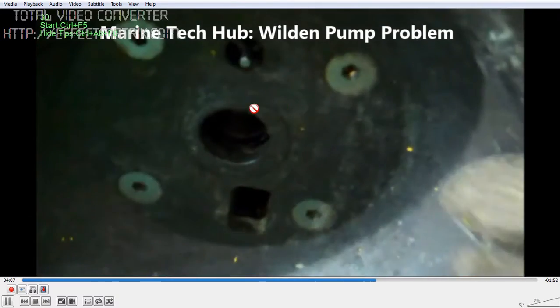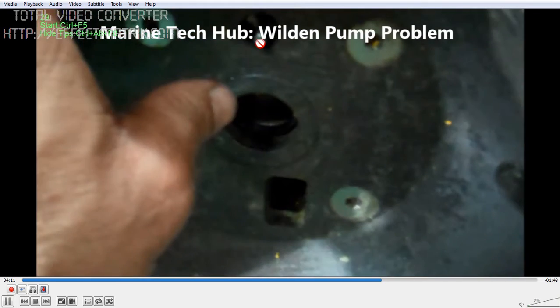One time the spool and diaphragm will push on this side, and the second time it will push on the other side. So this should move freely — if this is not working, your Wilden Pump will not work. If the spool piece is working then it is okay.